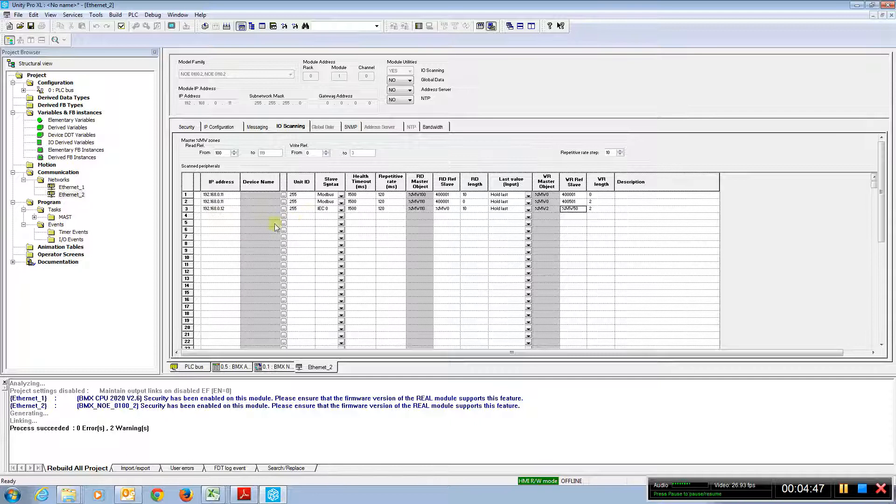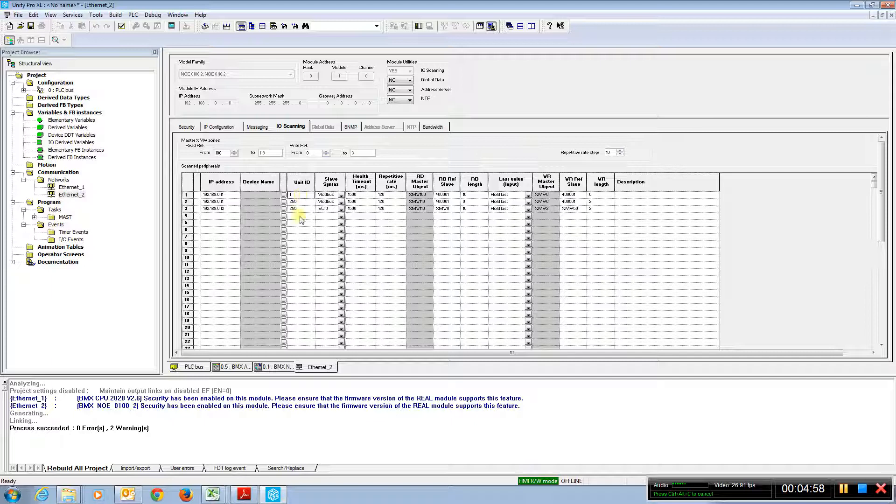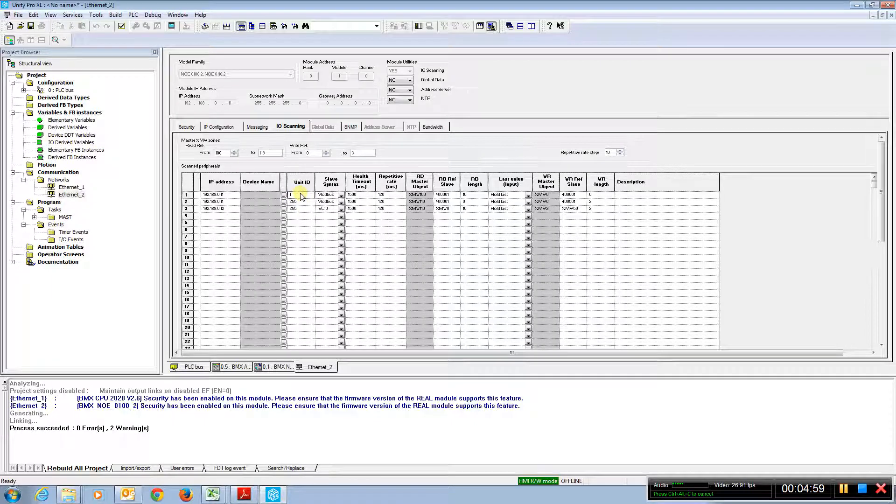Some other special things is we could actually have, if we were going through a gateway to Modbus on the serial side. If we were going to Modbus address one, we would simply put a one in here. And coming through the gateway, that would be the Modbus address of the device going through the gateway.